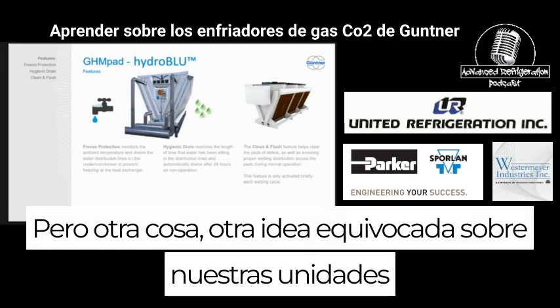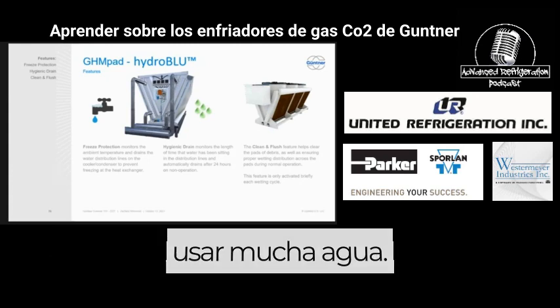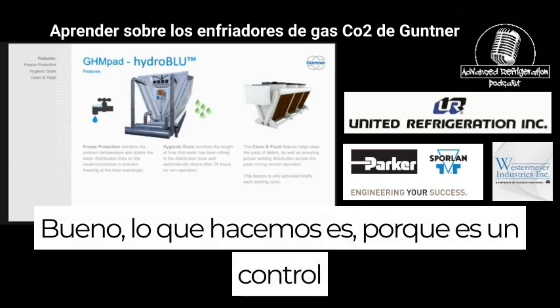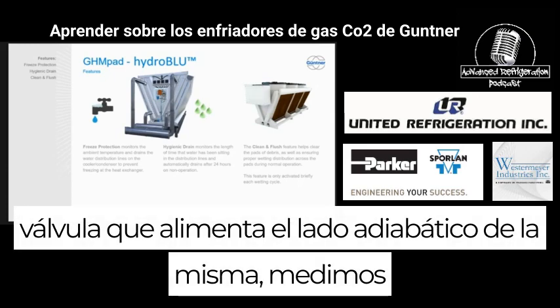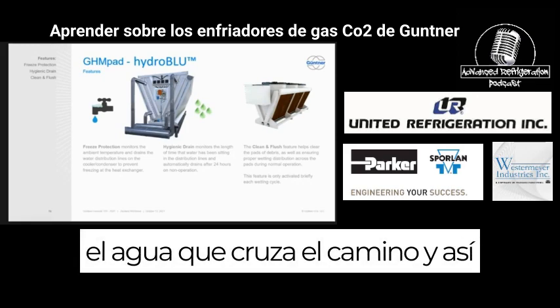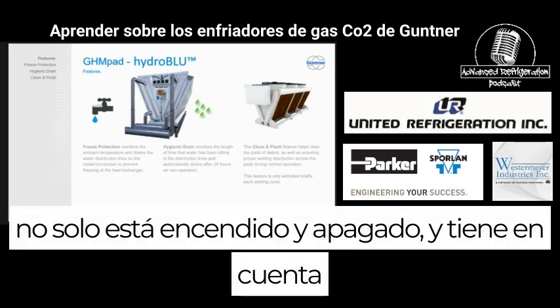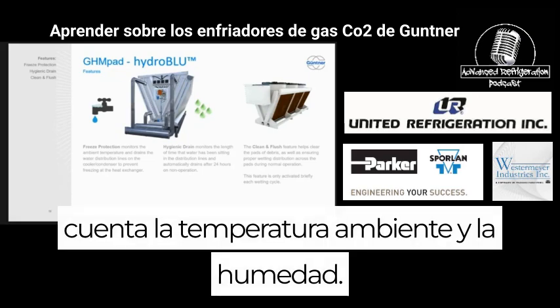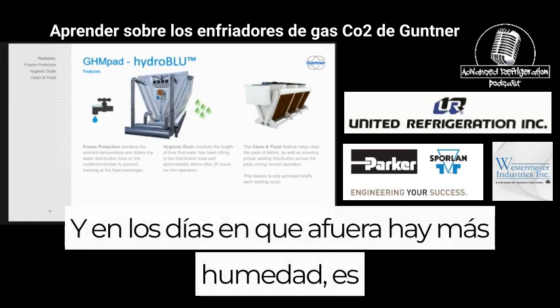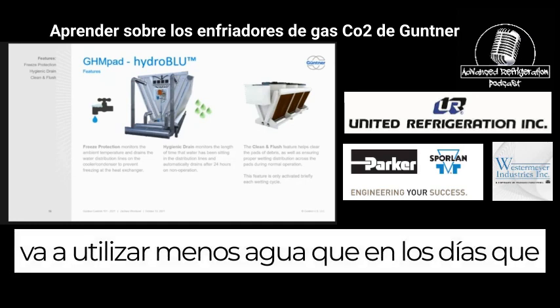But another misconception about our units is that they're pump and dump and use a whole lot of water. Well, because we have a control valve feeding the adiabatic side, we meter the water that goes across the pads. So it's not just on/off, and it takes into account the ambient temperature and humidity.